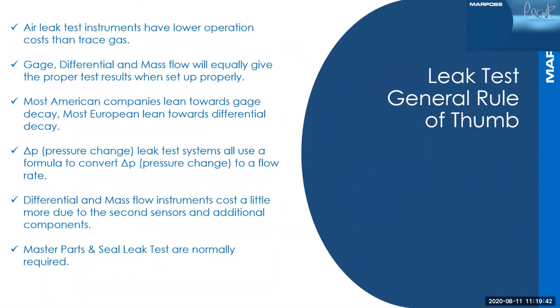General rules of thumb on this: air leak test instruments have a much lower operation cost than trace gas. Gauge, differential, and mass flow will equally give the proper test results when set up properly. I see a lot of argument on this, and depending on which company you're talking to, some will tell you that pressure decay is the only way to go. Others will tell you it's differential, and mass flow will definitely factor into that equation. All three, when set up properly, will give you the same result.